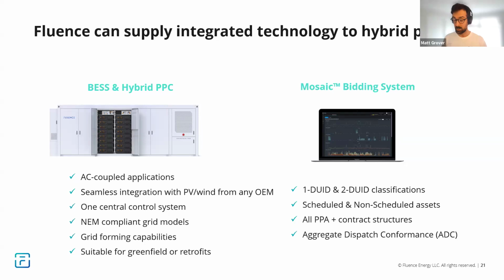Short answer is yes, with two caveats. One, assuming your physical kit can do that. From what we understand, some DC coupled inverter solutions have caveats or limitations about how much grid charging they can do, and often they can't charge at the same power level they're registered to discharge at. So assuming the plant is technically capable, yes, you could dispatch your battery to avoid curtailing your renewable plant, but only if the AEMO flags allow you to.